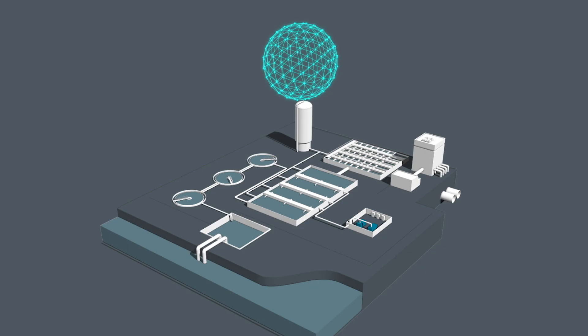Lastly, for end users of assets connected to critical infrastructure, or if end users have asked us to meet a particular security assurance level defined by IEC 62443, we have tried and tested data diode units that air gap our Edge device from the downstream control system, meaning that no information or data can be passed back down the stack.